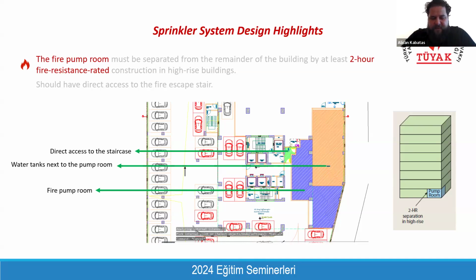Since statically solving these heavy pieces of equipment is very challenging, they always prefer to locate them on the lowest basement floor, so that all the load is supported by the ground, and you don't need to find a challenging solution from the statics point of view. That's why generally the fire pump room is located on the lower basement floor.